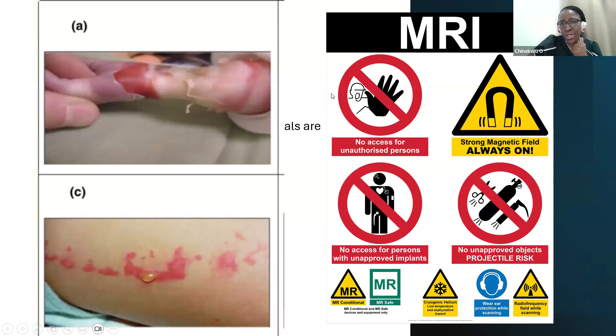Now, this is a child who I think someone forgot a pulse oximeter on. This is a 5-month-old baby, who went in to have the scan with a pulse oximeter left on, because the other risk from MRI is burns. It's because you can transmit the RF pulses through materials that can conduct electricity, be it electrical substances, electrical material in contact with the patient, or other things that can conduct. So for this child, unfortunately, it was a pulse oximeter that was connected when they had their scan, and it just conducted a lot of RF pulse to that arm and basically led to a degloving injury.